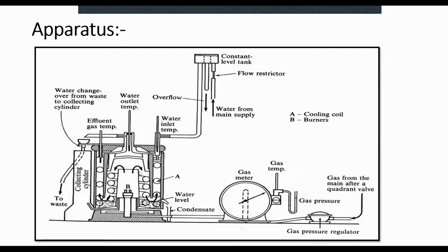It is like our home, like a gas cooker or something, but here the gas meter is different. We are measuring the flow rate or the volume going through this gas meter. We have to measure the gas supplied to the furnace.